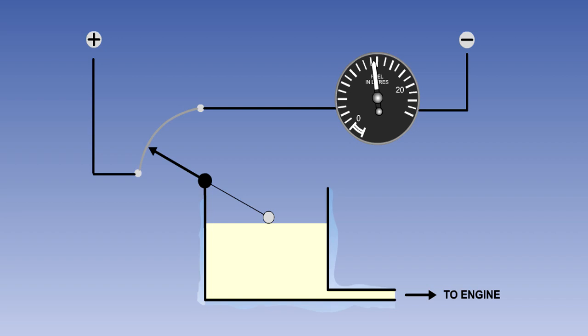Secondly, this type of system cannot compensate for changes in the specific gravity of the fuel. So, as the fuel gets colder, the indicated quantity will decrease and vice versa should the fuel temperature increase.